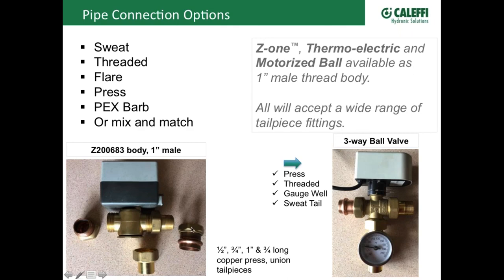But when we make a body like this, now look what it does. It gives us all these different choices for connection tail pieces. So in this picture I'm showing, there's a 3/4 male thread, a 3/4 press, a 1-inch press. I think that's a 3/4 sweat there. So think about this. I know a lot of the contractors back east are still using speedy headers, which is a welded steel header that gives you a threaded connection to come off their boiler. So this valve you could screw right into the speedy header, and then on the other side you could go to copper, you could go sweat, or you could go to PEX.